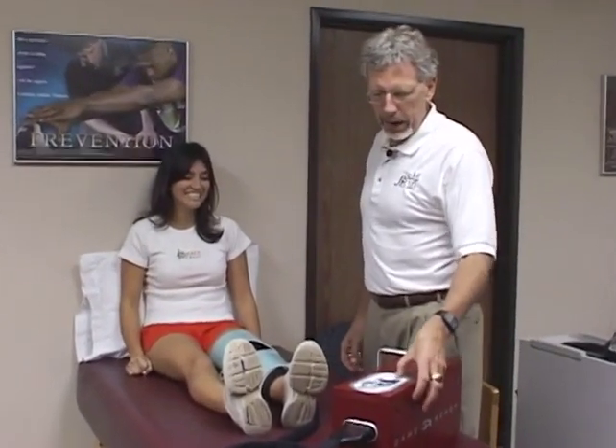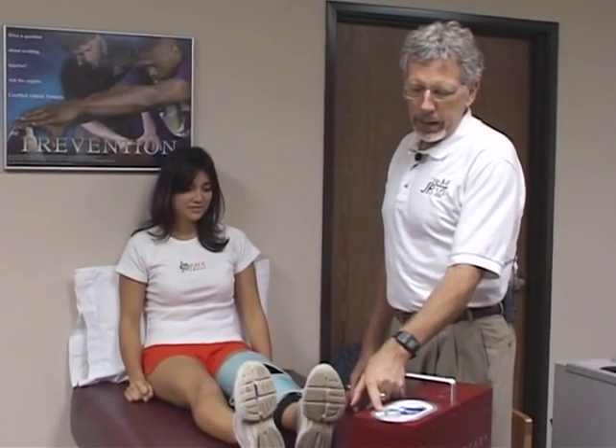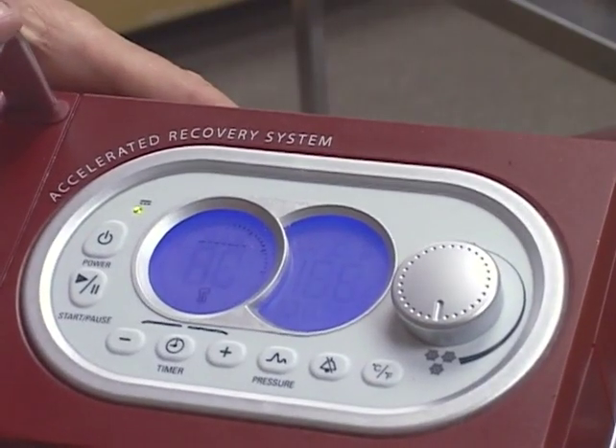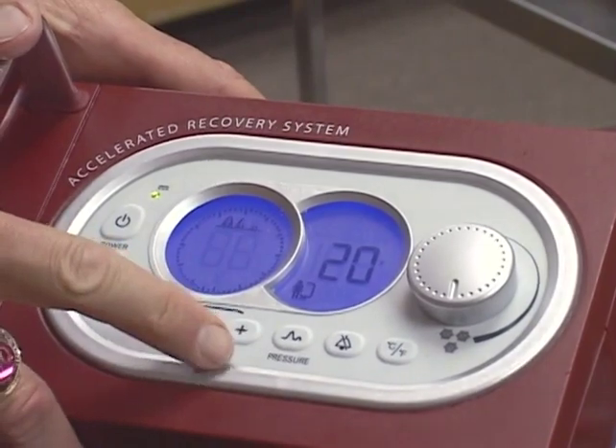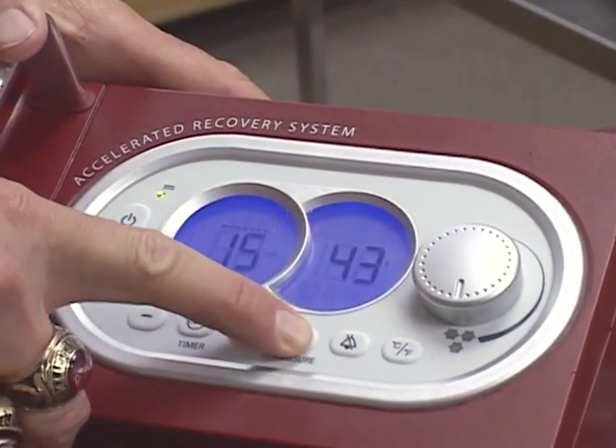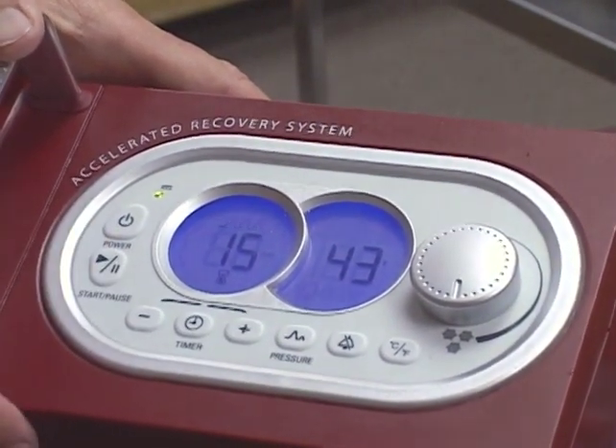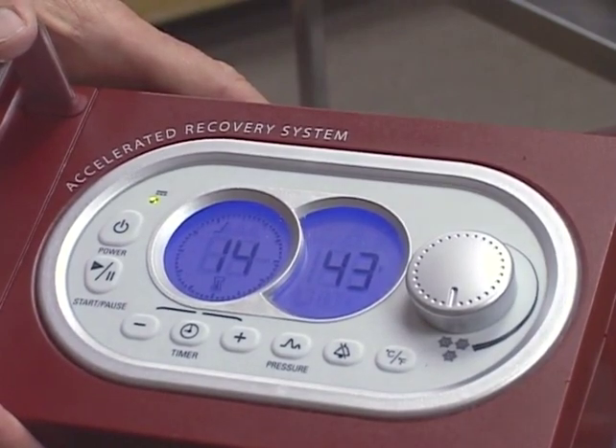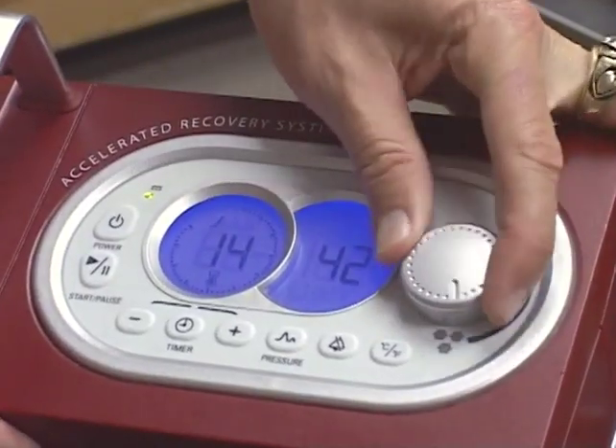So we'll go to power, and that's the first thing that occurs. Once we have that, the adjustments that we have here, we can adjust so we can read it in Celsius or Fahrenheit. We can have a bell timer on this thing, and then we can do the pressure. She's got quite a bit of edema in there, so we're going to shoot the pressure up as much as we can. We can also adjust the time here, and then we take it off of pause, and now it's going to go on and off, and this temperature, as you can see, is starting to drop. Right now it's at 42 degrees.